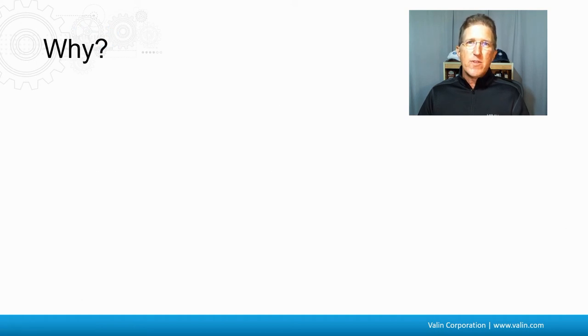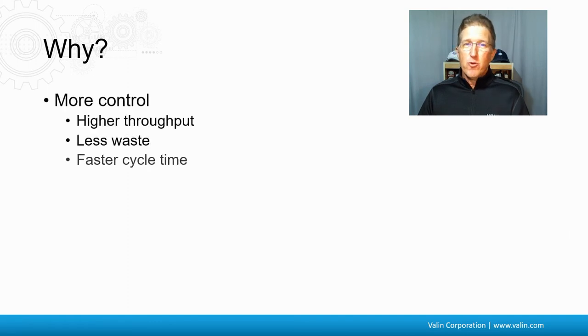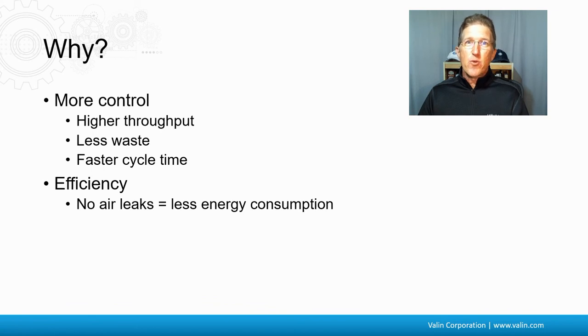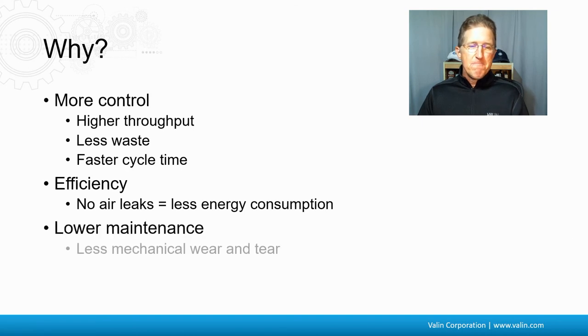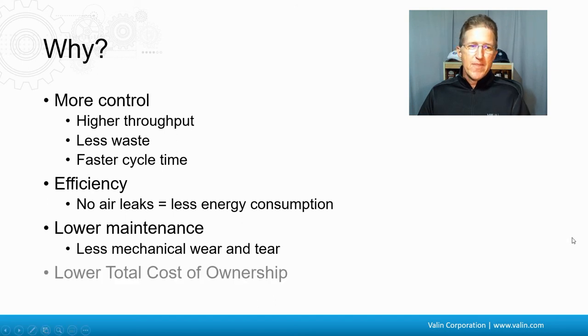You might still be wondering, why would somebody want to change from fluid power over to electric? Well, right off the bat, you get more control, which can lead to higher throughput, less waste, and faster cycle times with electric. Efficiency. You don't have any air leaks and the electric is more efficient than the fluid power options. And it leads to less energy consumption. And lower maintenance. Oftentimes the fluid power actuators have to be replaced on a yearly basis or more often because of that bang, bang. With electric, we don't have to do that. There's less mechanical wear and tear.